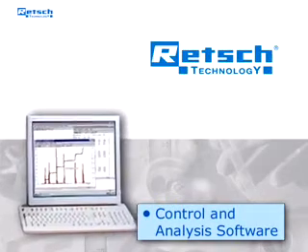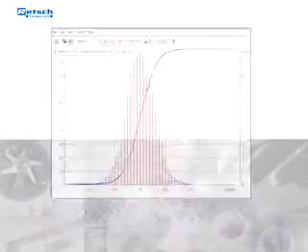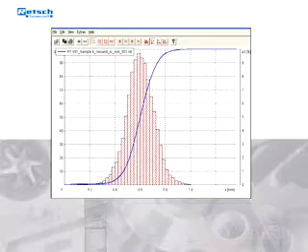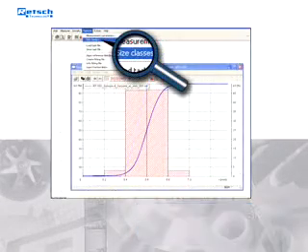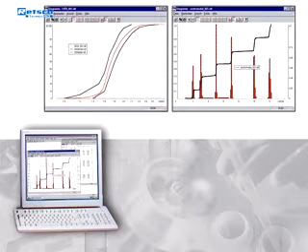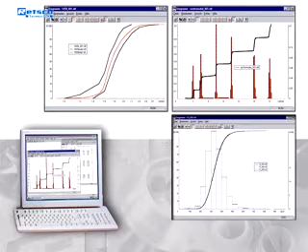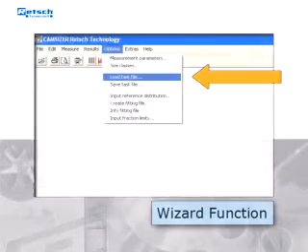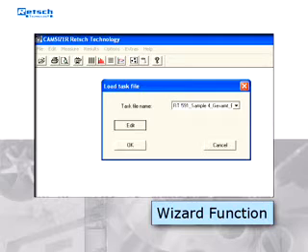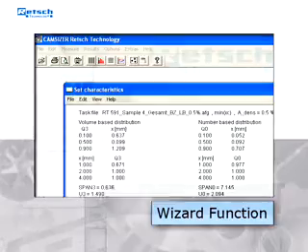The progress can be followed on the computer screen. Electronic processing of the instantaneous digital images takes place internally in 10,000 size classes, and the result is saved in at least 1,000 classes. The user can easily choose individual size classes to be displayed. RETSCH Technology supplies the Camsizer complete with a well thought-out and powerful control analysis software. All measured results can be displayed and processed in various ways with the application-oriented program. The so-called wizard function guides the user through the definition of a measuring routine for a new material, supporting the easy creation of standard operating procedures effectively.